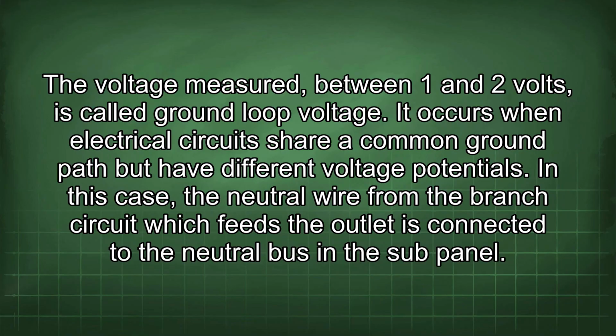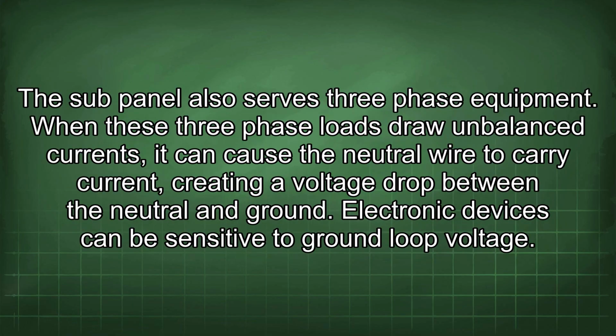Voltage measured between 1 and 2 volts is called ground loop voltage. It occurs when electrical circuits share a common ground path but have different voltage potentials. In this case, the neutral wire from the branch circuit which feeds the outlet is connected to the neutral bus in the sub-panel. The sub-panel also serves three-phase equipment. When these three-phase loads draw unbalanced currents, it can cause the neutral wire to carry current, creating a voltage drop between the neutral and ground.